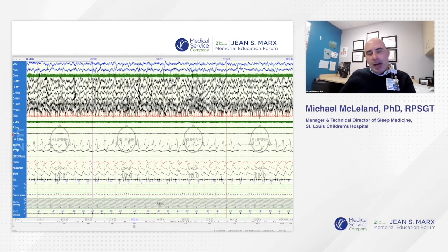The reason why we didn't start out with the therm channel was because we really didn't think we would see much fluctuation in temperature with the breathing coming in versus going out, just because of the high humidity. It means it's a lot warmer air going in, and it's about the same coming out. So we didn't think we'd see much fluctuation, but once we tried a patient, we saw that we did have a good channel and a good signal.